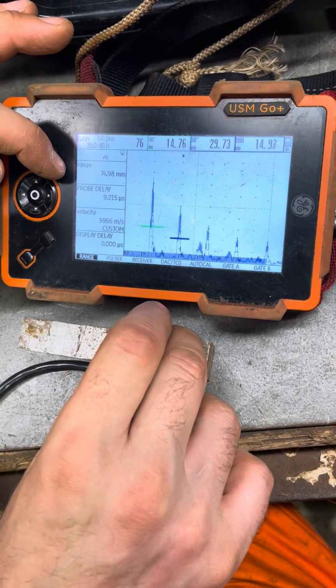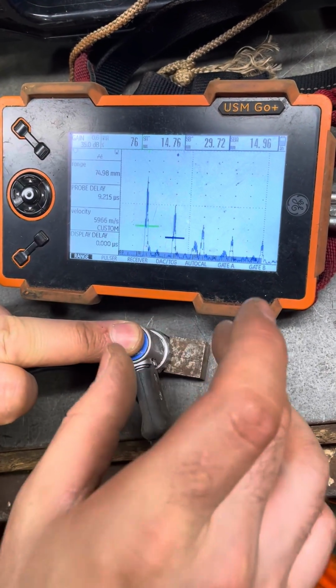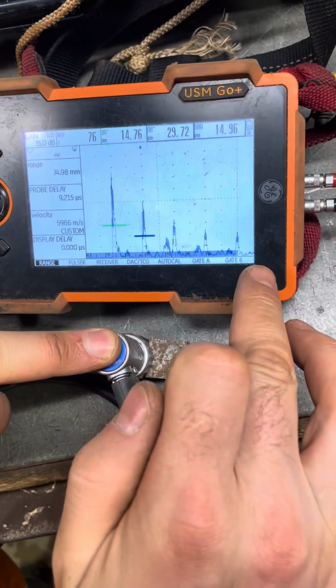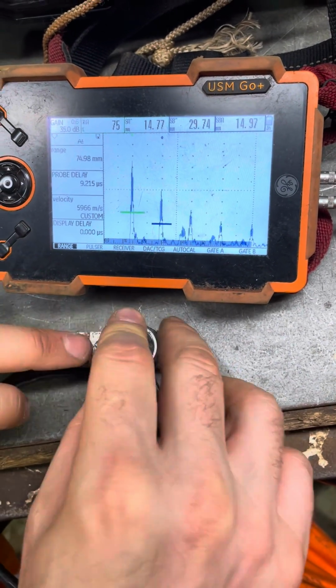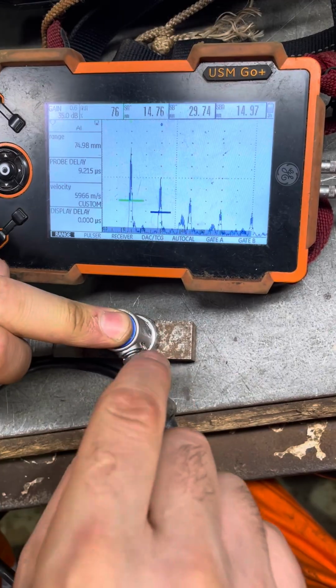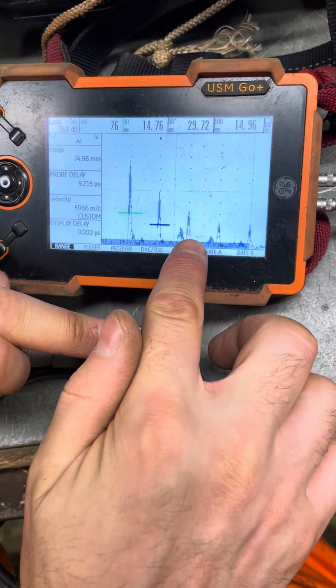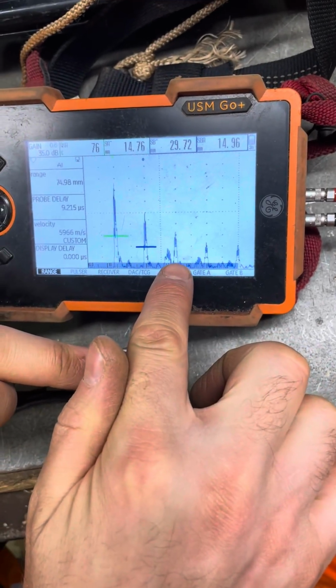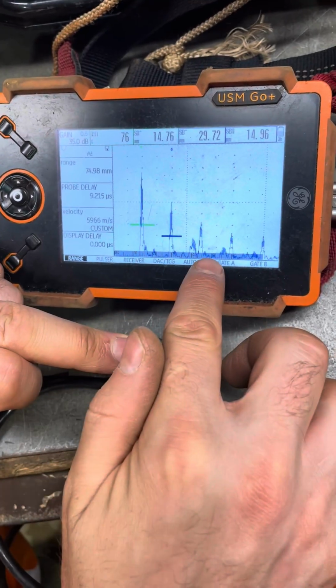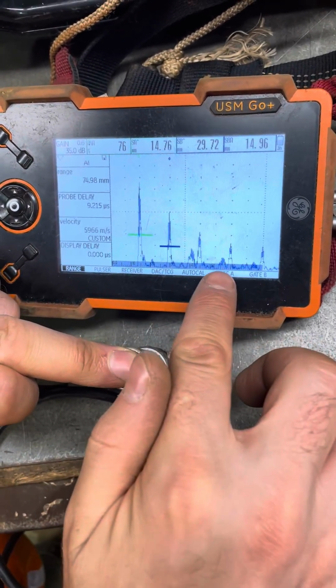What is range? Range is the distance that we will see on the screen. So if we're calibrating at 15 millimeters, the distance should always be such that we always see 3 signals. 3 signals. And they are bigger, smaller, and smaller. There could be 4 or 5. But you should see at least 3 signals. Right now we see 5, which is fine.